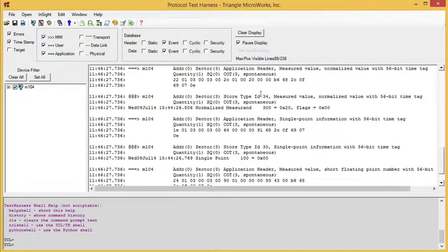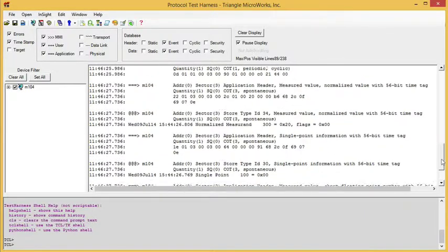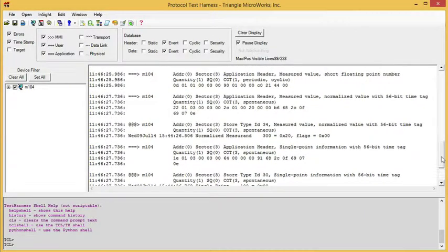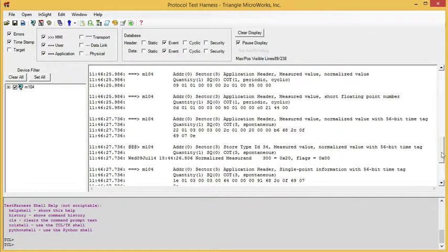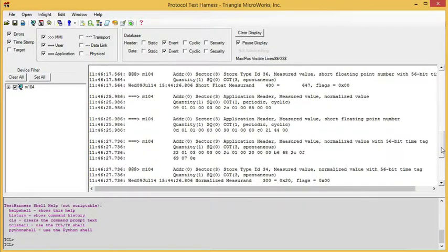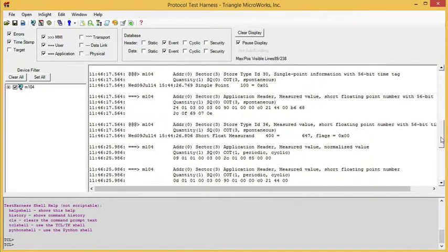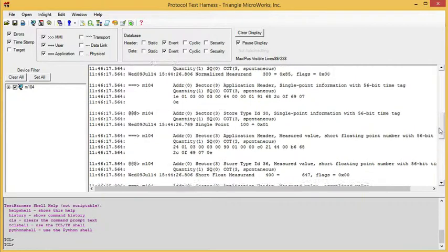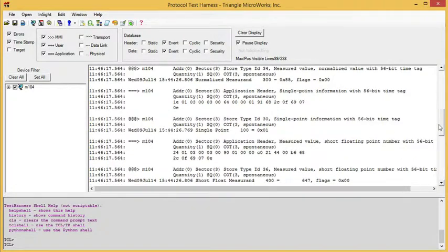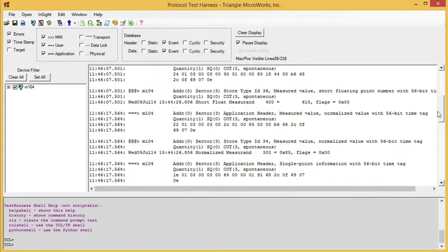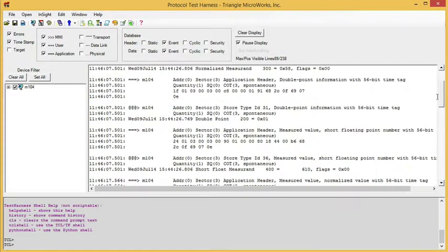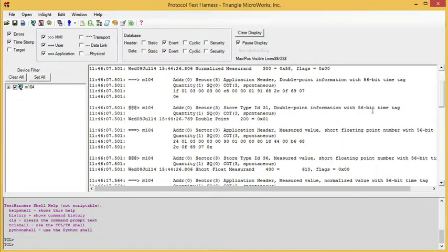I have a type ID 34, a measured value normalized value with 56-bit time tag. And I have a double point information with the 56-bit time tag. So as you can see, the gateway is now reporting data with the 56-bit time tag.